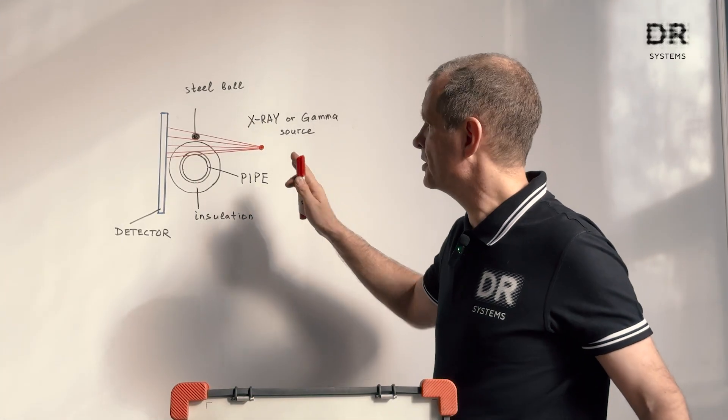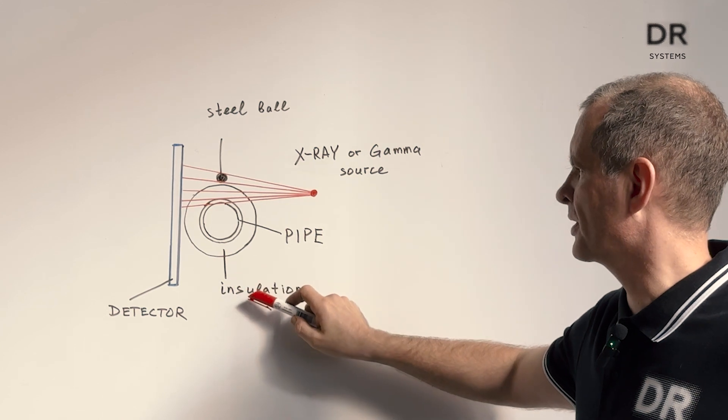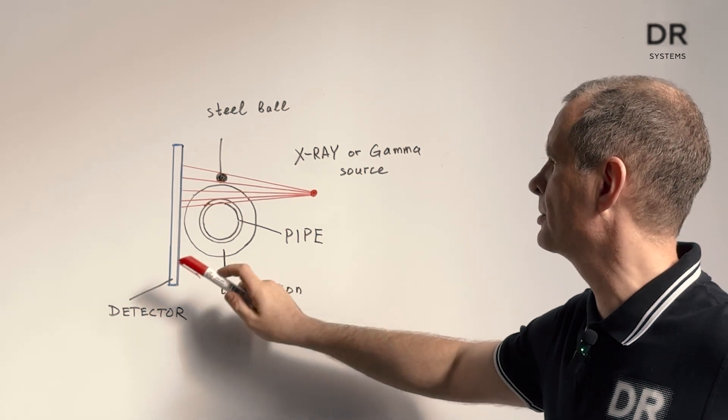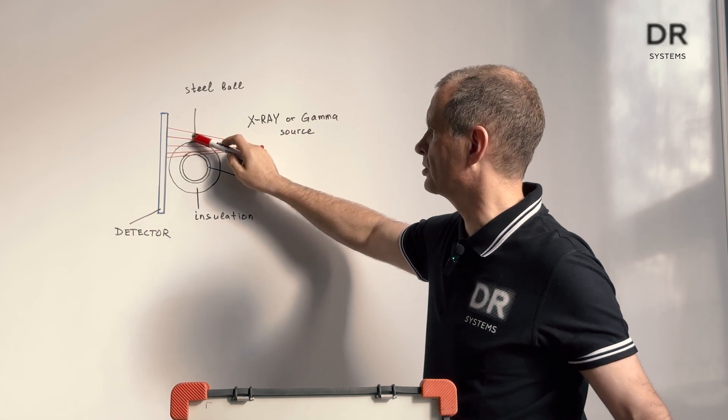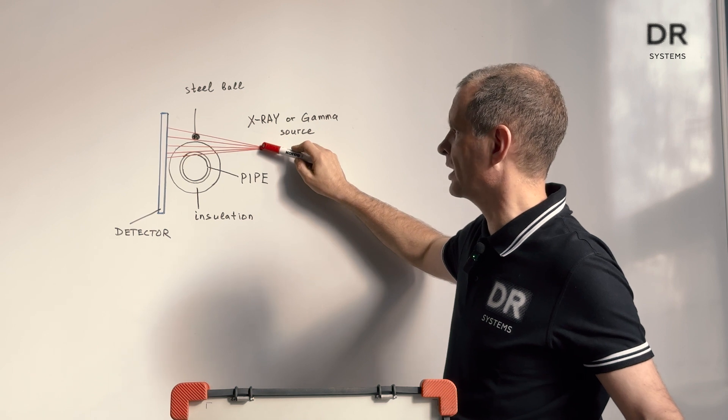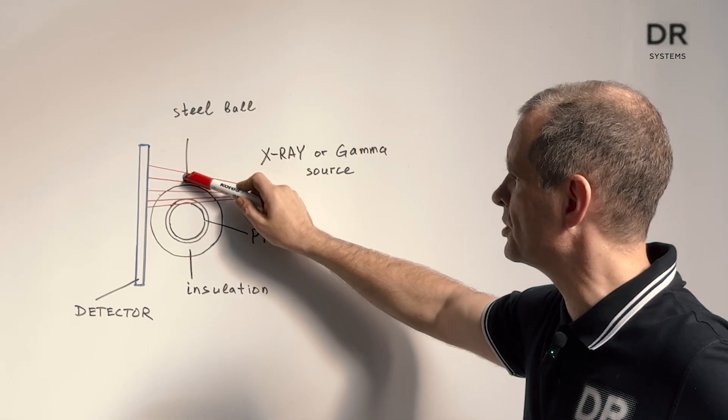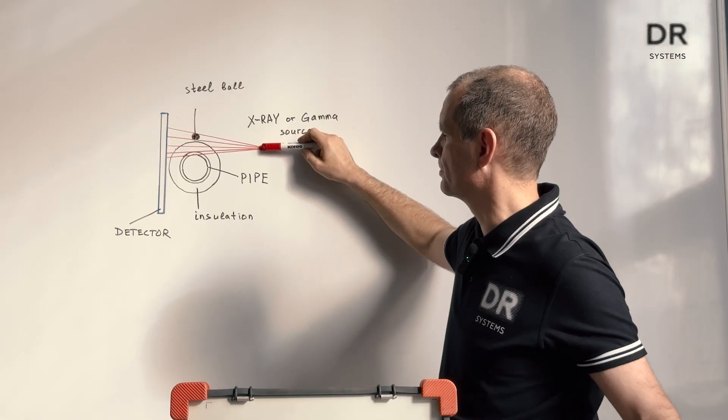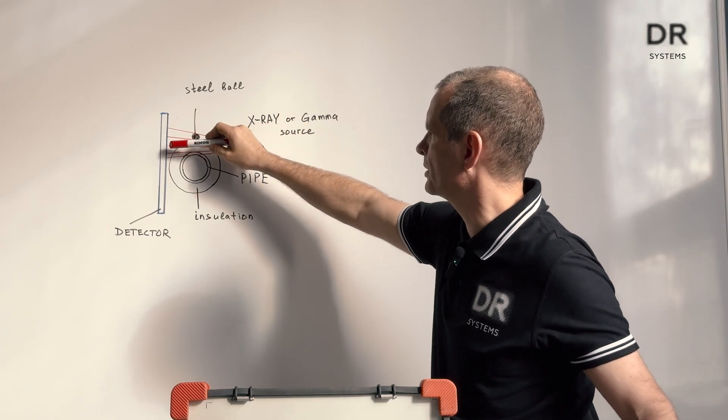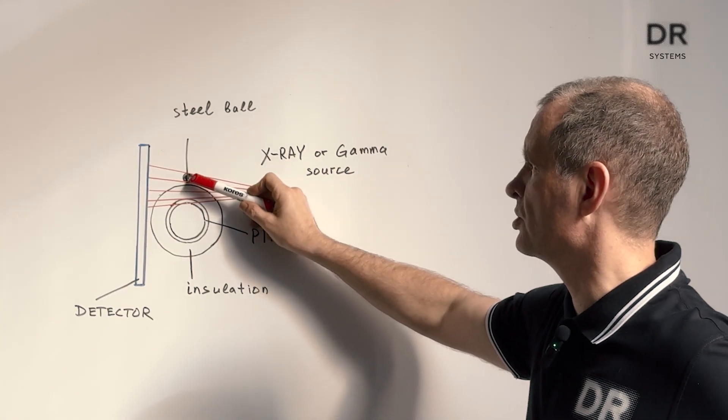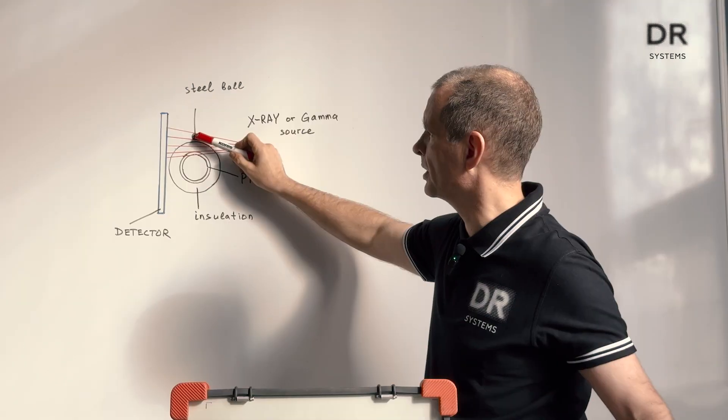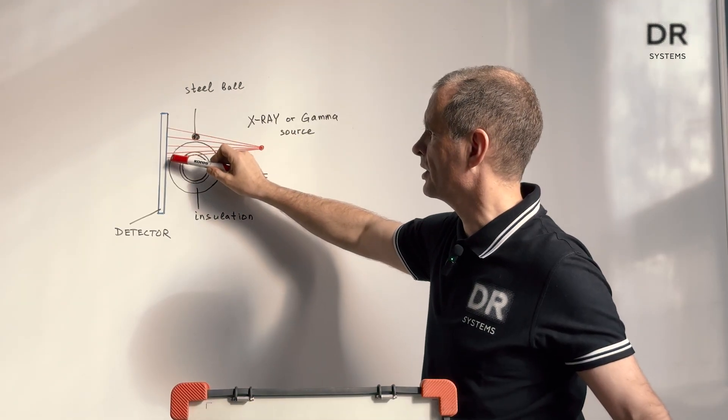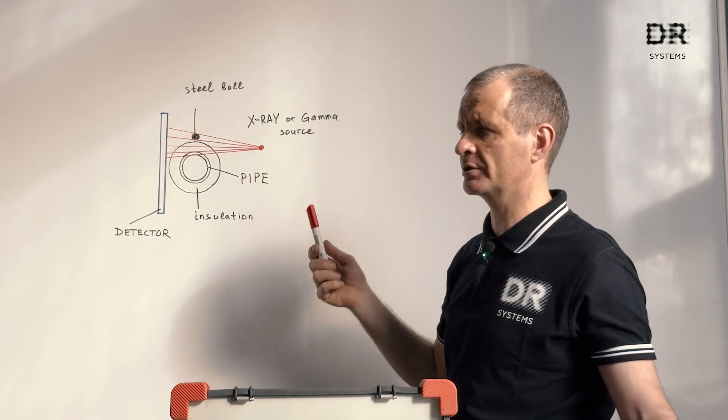Here's the idea illustrated by our simple picture. The pipe is inside, here is the heat insulation, the detector is behind the pipe, the steel ball is here installed on the insulation and here's the right place for the x-ray or gamma source between the steel ball and the pipe wall on this line. Not here and not here but right on this line. This will give you the same geometric amplification factor for the steel ball and for the pipe wall. Therefore your measurement will be more accurate.